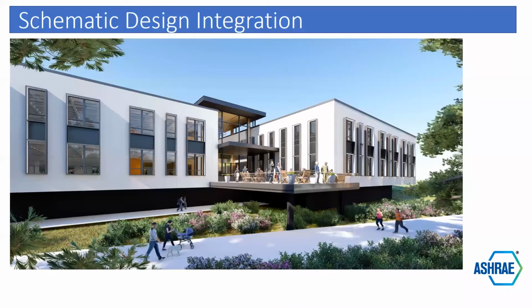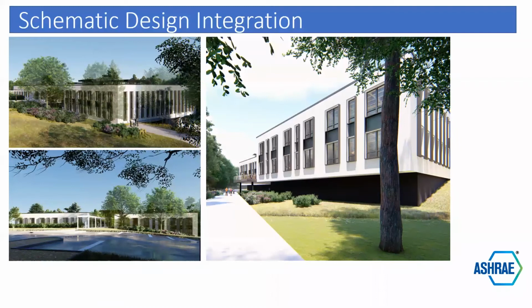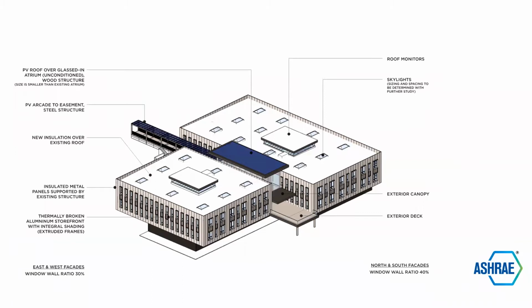and ended up with the schematic design of the perimeter as shown on this diagram with the windows and this shading in the critical areas around the window settings. And this is how it's integrated into schematic design. And if you noticed at the beginning, we had a barrel roof over the center area, and this was replaced with a flat roof. Which really helps us in terms of solar gains and allows us to keep that area much cooler and use less energy.